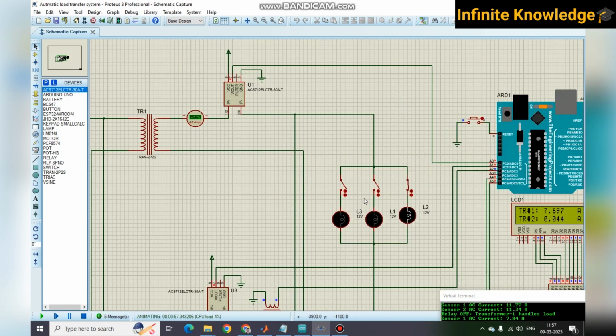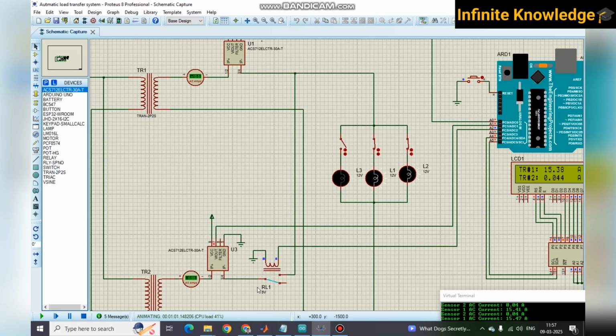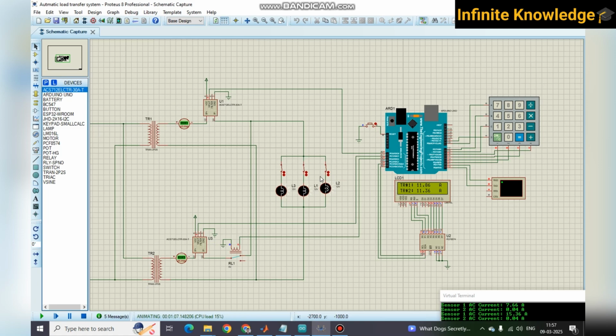Now if I increase the load again, let me check, it is only 15, which is less than 20. That's why this one does not come into the picture. TR2 will come into the picture only when the ampere is greater than 20. As I start the system, my ampere increases to greater than 20, which is 23.15, and it turns on TR2. Both are sharing the load. So in every scenario, it is working very clearly.